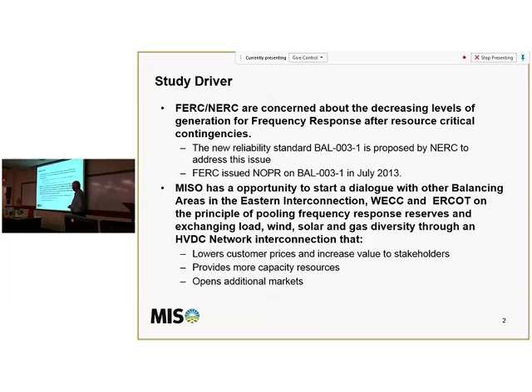We had an opportunity to look at that frequency response problem, and I started looking at a way to exchange power with WECC and ERCOT, so that we could pool the frequency response obligations of the three areas together and use the DC system to exchange power when one person needed it. The other two would give them a contribution, and vice versa. Until this year, it wasn't possible to do that technically because the DC ties couldn't reverse fast enough for frequency response obligations.